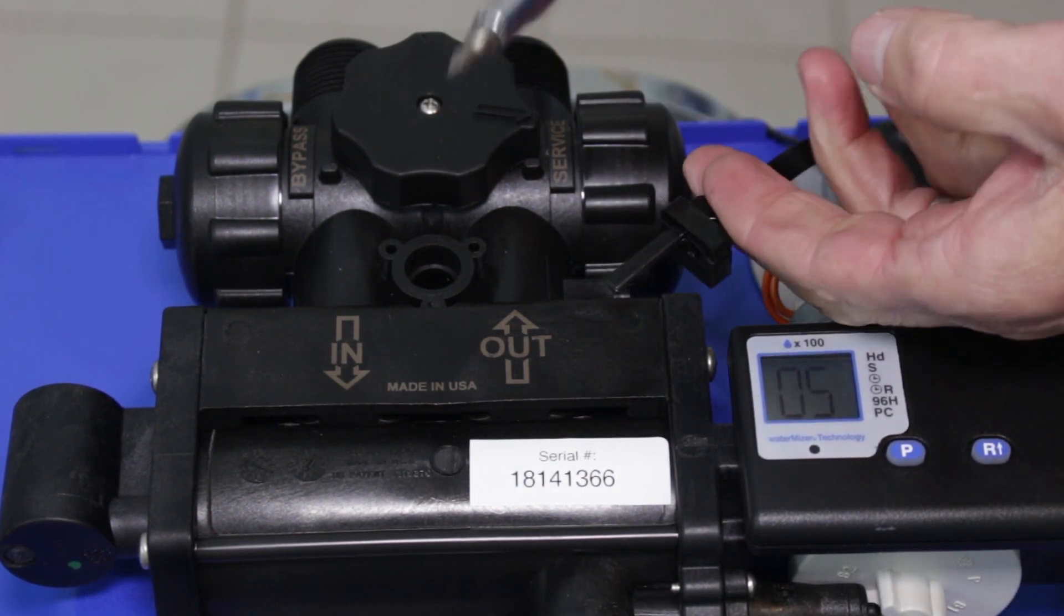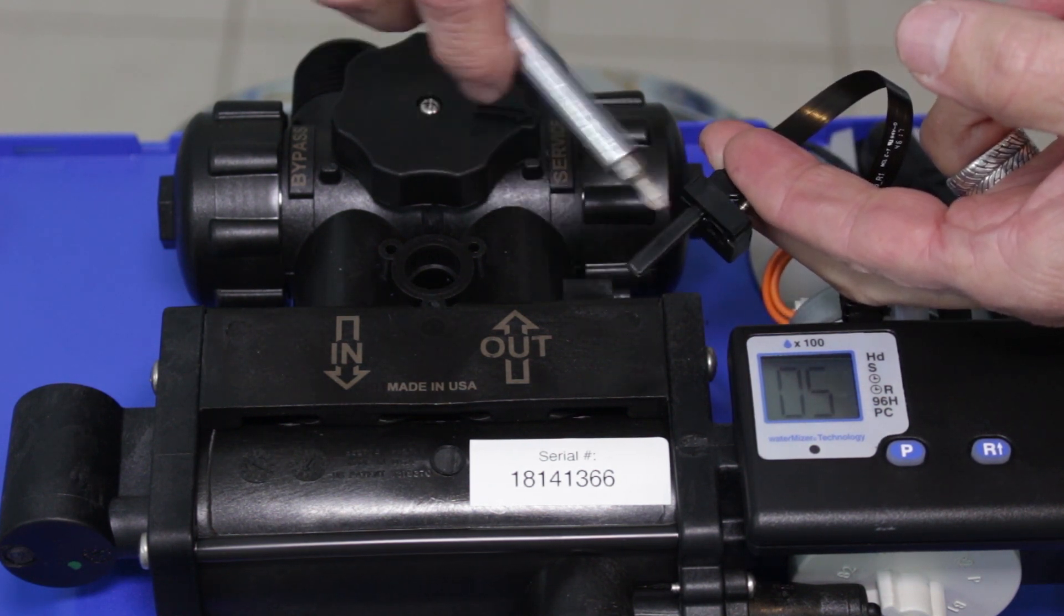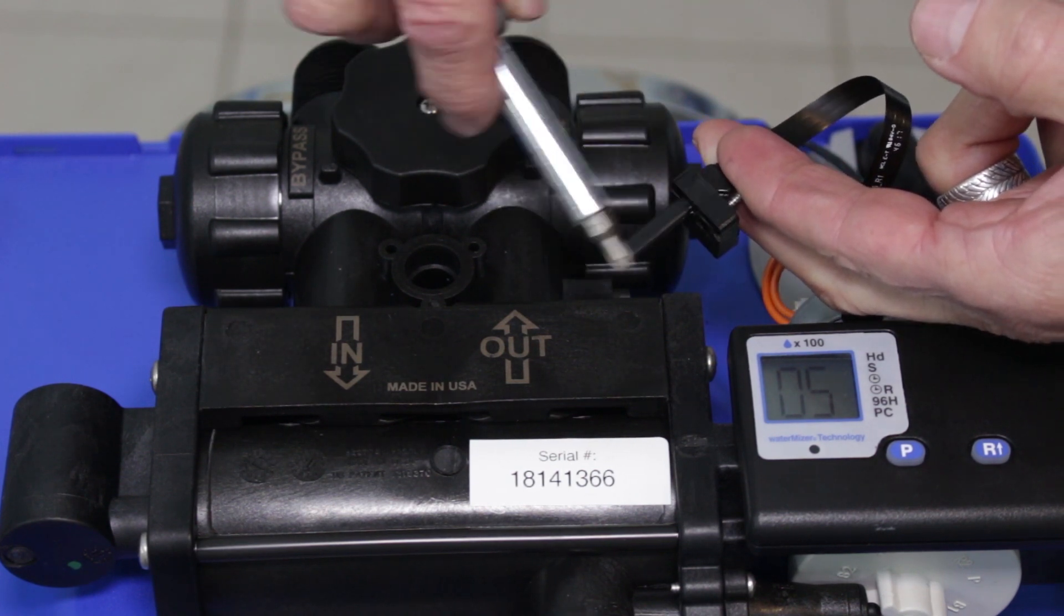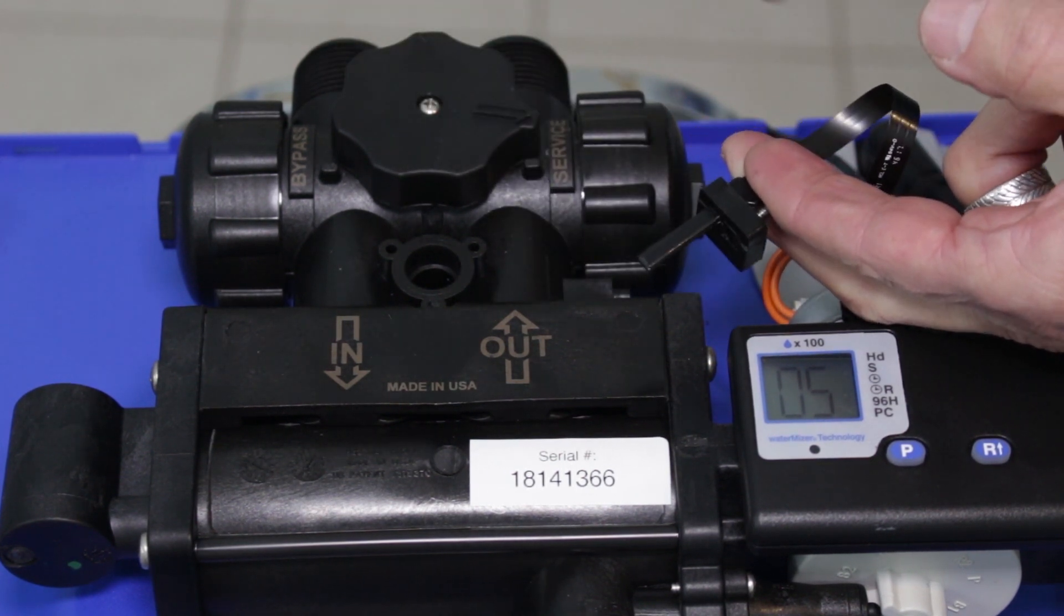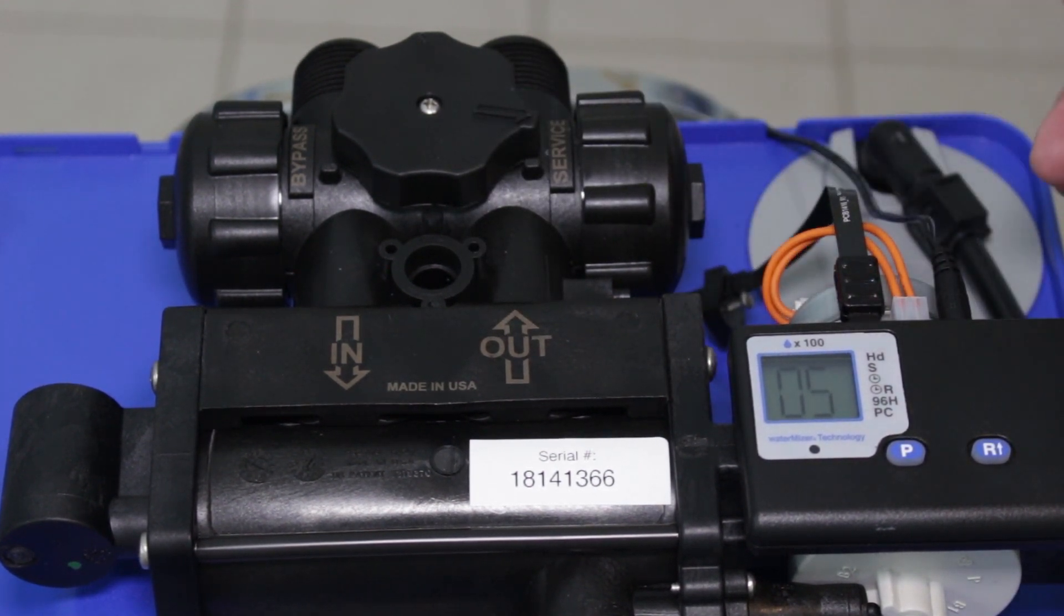You can test it by running a magnet. This is a magnetic screwdriver. When you run the magnet over here, this light should be flashing. If it isn't flashing, then there's a problem with the turbine inside here. I'll show you what that looks like.